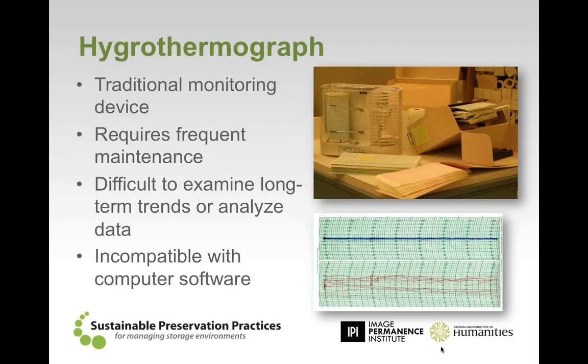And one other thing I like to bring up is the human error that plays a factor in this. Jeremy and I were working at a museum, and the month before we left, while we were getting our data together, I asked for any information they may have. And if you look at this bottom graph, this is unfortunately what they sent to us. It's great that they're monitoring. However, the flip side is that it's useless to us. It's just been going round and round and round. So the data that they recorded, by not pulling that off, just tells us the highs and lows the space experienced.